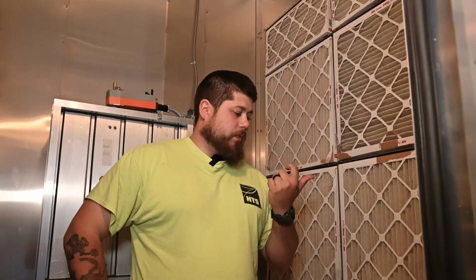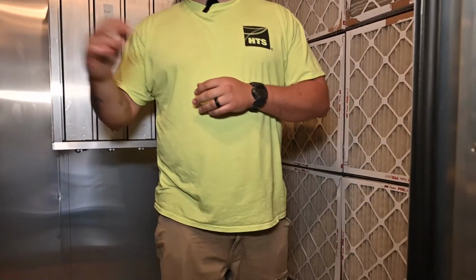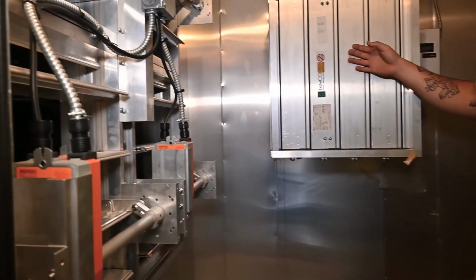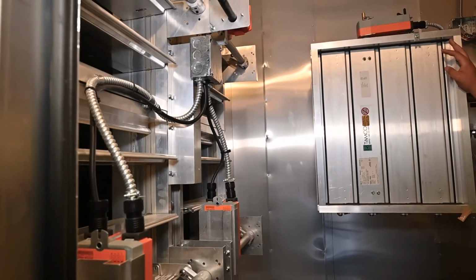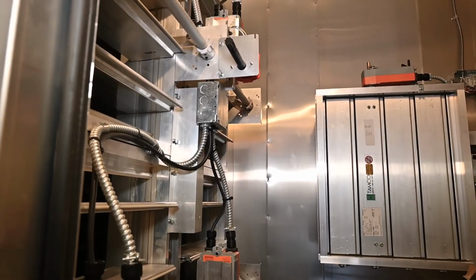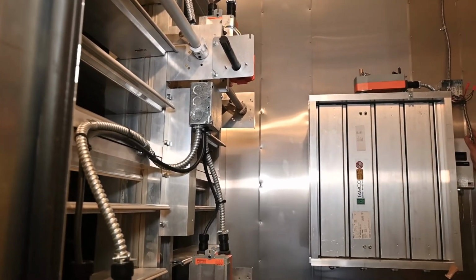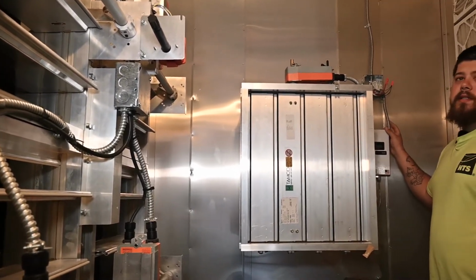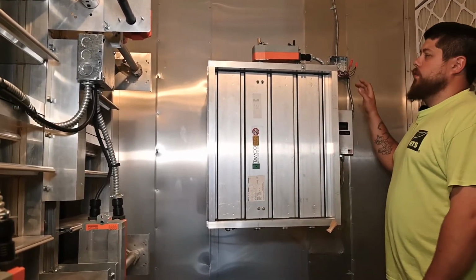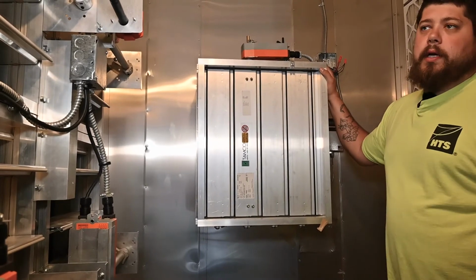Okay, this is our mixed air section here. Again, another set of pre-filters on this side. Same thing goes for the ones I just mentioned. My recommendation of replacing them is all going to be based on location and how fast they get dirty. Right here we have our return air coming into the unit, and then our outside air. Next to the outside air damper here, we have an Ebtron flow station. This flow station, nothing needs to get done to it, but it does display what the outside air CFM is coming into the unit. This reverts back to Zenergy and allows them to see what we're doing.